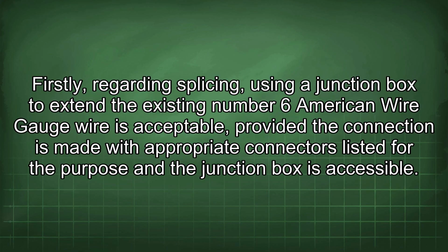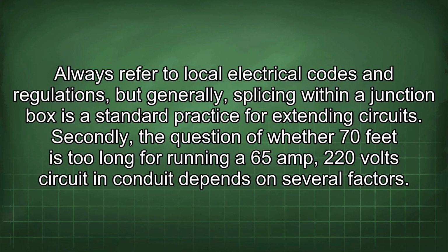Firstly, regarding splicing, using a junction box to extend the existing number 6 American wire gauge wire is acceptable, provided the connection is made with appropriate connectors listed for the purpose and the junction box is accessible. Always refer to local electrical codes and regulations, but generally, splicing within a junction box is a standard practice for extending circuits.